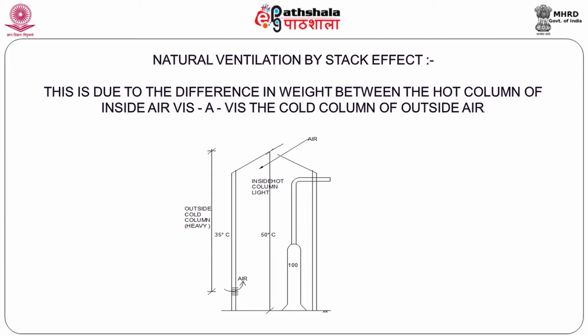The moment this becomes light, obviously by the law of nature, by the law of gravity, this tries to go up and outside air tries to rush in through the lower openings. Now that is the stack effect. This is extremely useful for industrial buildings like boiler houses and cement plants, where occupancy is virtually zero.